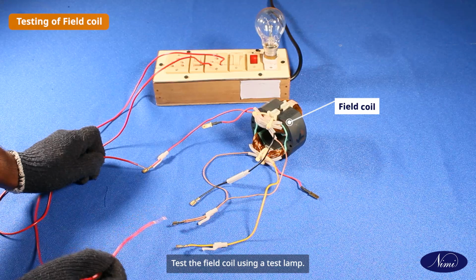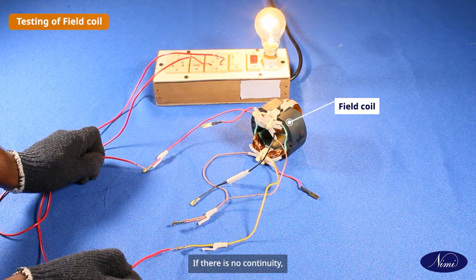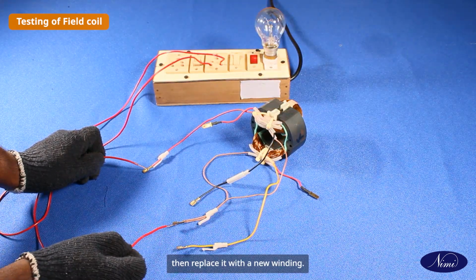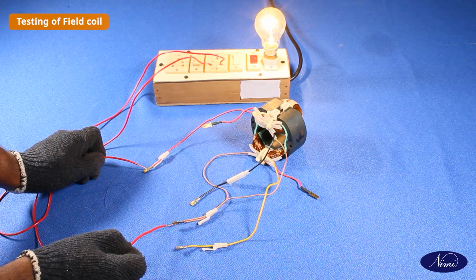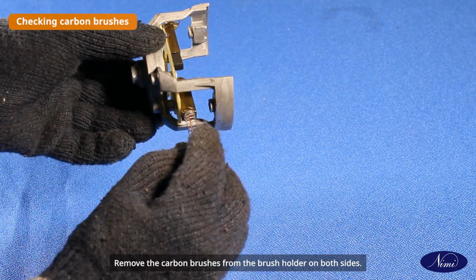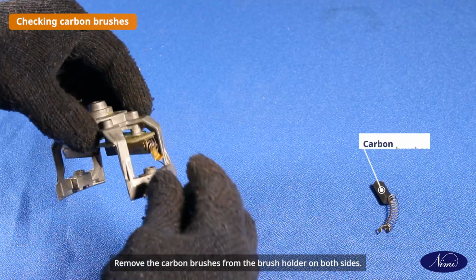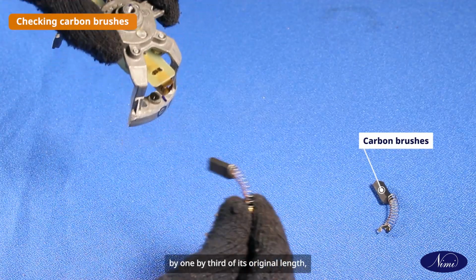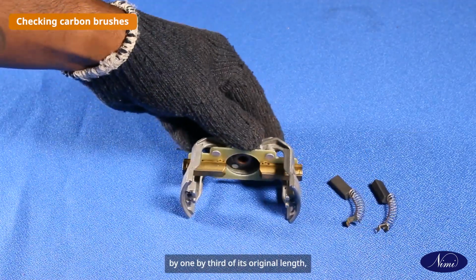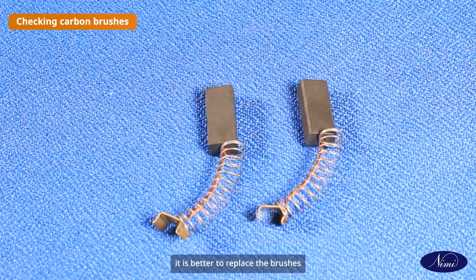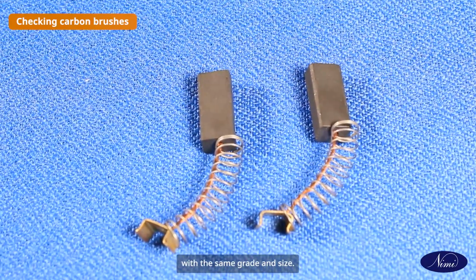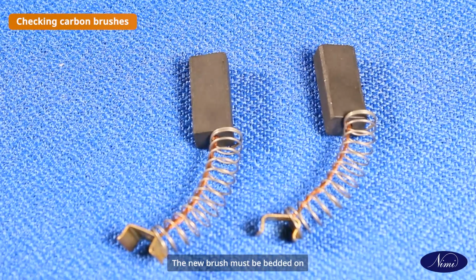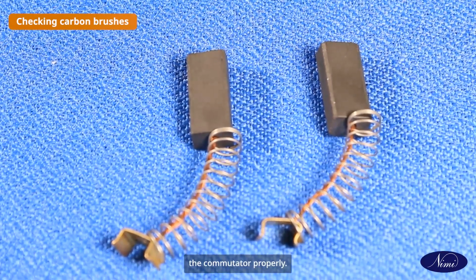Test the field coil using a test lamp. If there is no continuity, then replace it with a new winding. Remove the carbon brushes from brush holder on both sides. If the brush length is shorter by 1/3 of its original length, it is better to replace the brushes with same grade and size. The new brush must be bedded on the commutator properly.